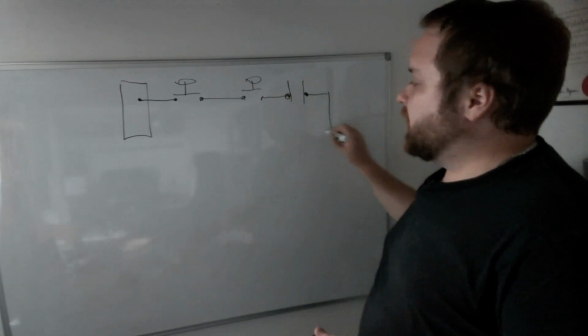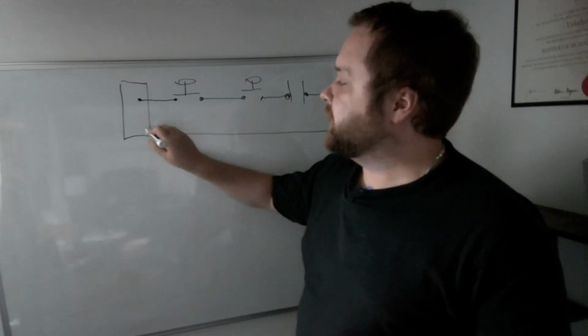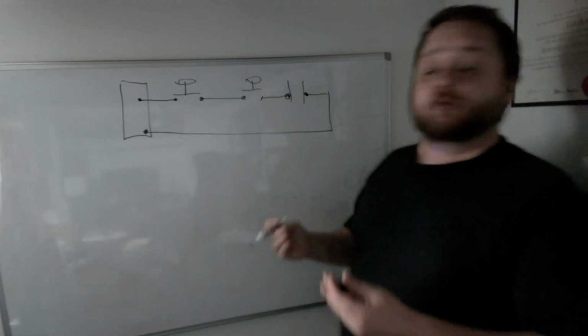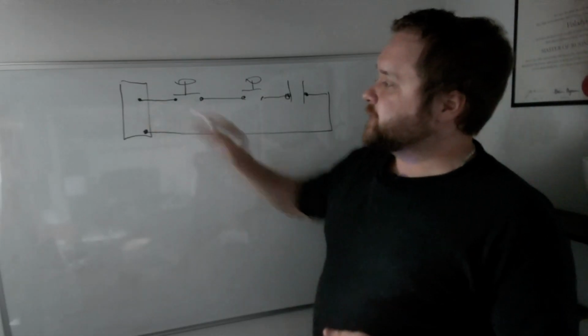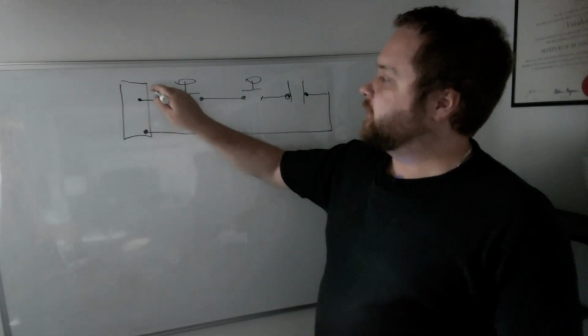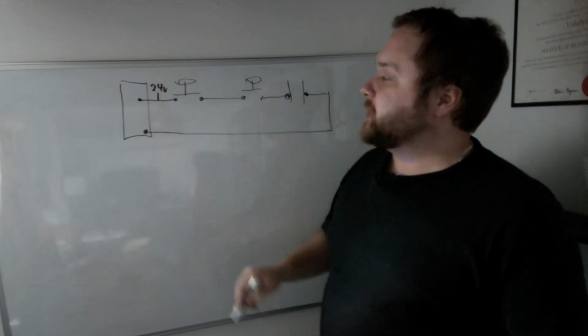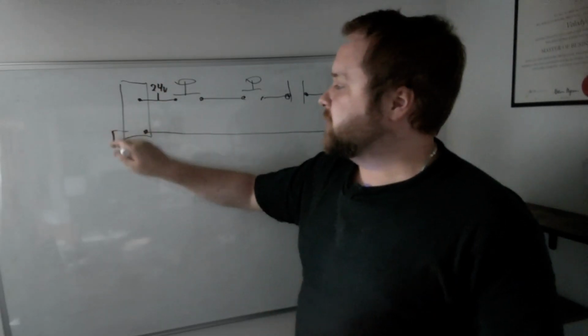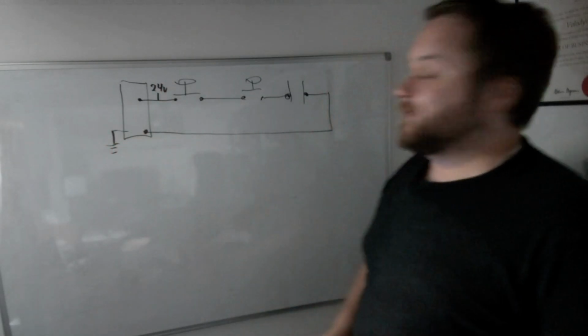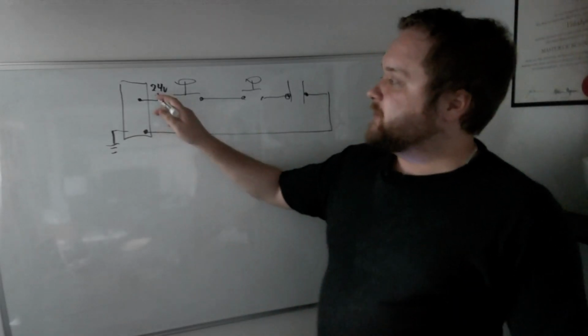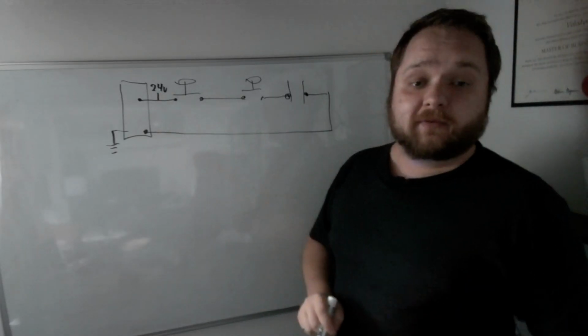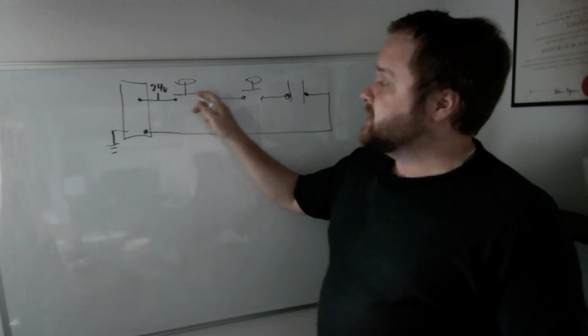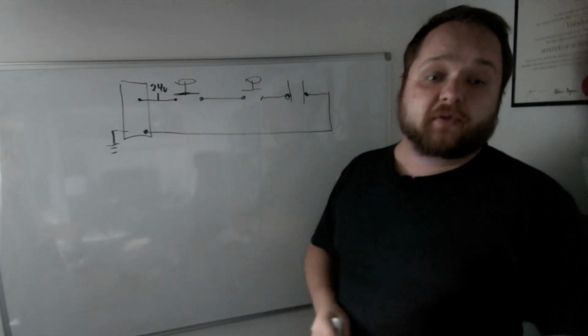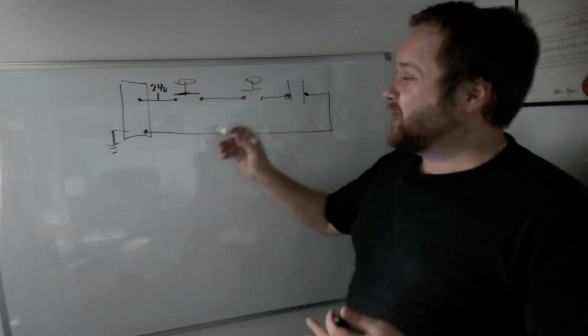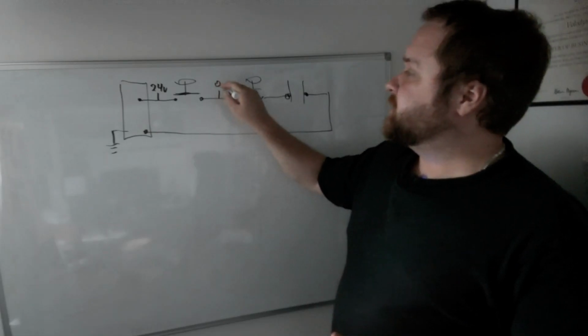And so this wire is going to come back to your relay and come in right here. Think of this as one single channel. The relay is going to emit 24 volts. Here, if I bring in my voltmeter, and of course it's going to be connected to ground or 0 VDC, if I measure the voltage here, currently it's 24 volts. Right now, as you can see, my e-stop is hovering above both of those points, so it is not allowing the signal to go through. So here we have 0 volts.